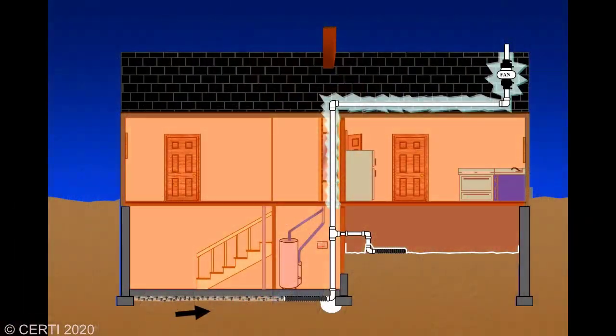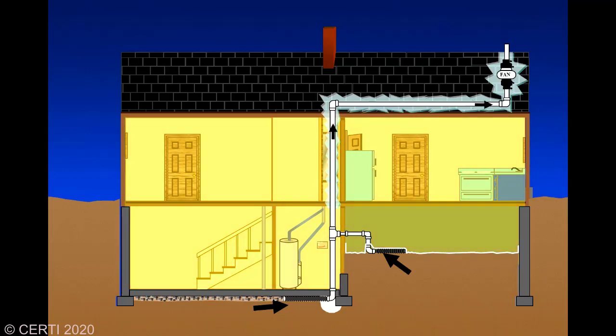Active soil depressurization, or ASD, is a method for reducing radon entry by creating a vacuum under a building's foundation that is greater in strength than the vacuum applied to the soil by the building itself, and preferentially collects the radon before it gets into the building and exhausts it to a safe location outdoors where it will not re-enter the structure. By reducing the internal vacuum within the building via HVAC system repairs, the ASD system does not have to work so hard since the interior vacuums have been reduced. Let's take a look at how ASD works.